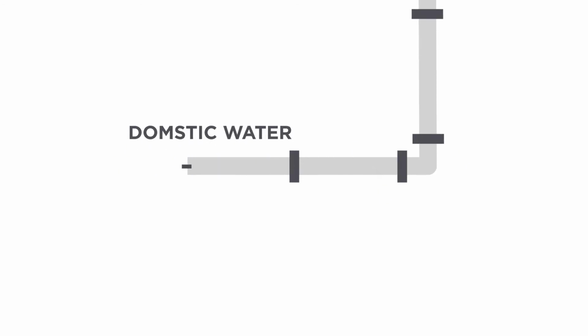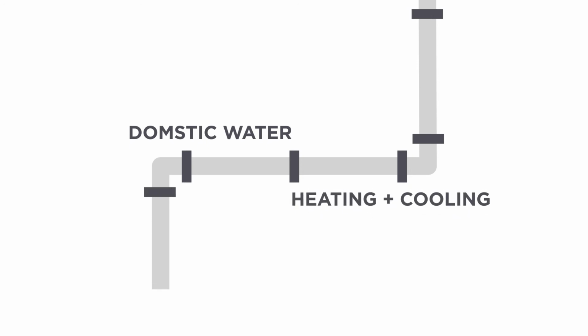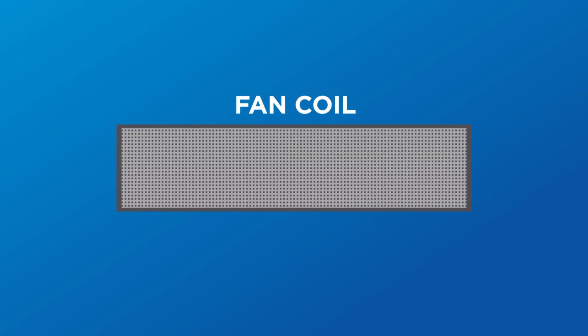With IPS, the domestic water piping is used to provide not only the domestic water, but also for heating and cooling the space as needed. The same pipe that feeds the shower and sink also feeds a terminal unit which is placed in each space that requires heating and cooling. A terminal unit is not just a normal fan coil, it's actually a coil built out of NSF 61 certified copper, rated for potable water use.